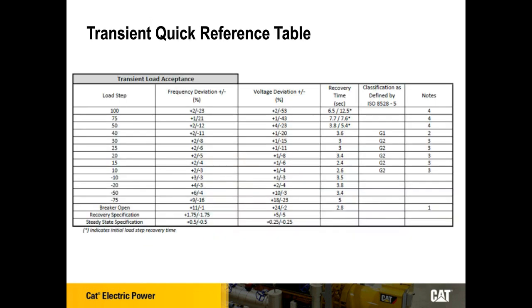This is the quick reference table on the same sheet, and this is important if you're doing a rough design for a project and trying to decide if one size generator or another will work for the size loads you have. It shows for a given load step what the frequency deviation, voltage deviation, and recovery time will be, so you can quickly size a project roughly.